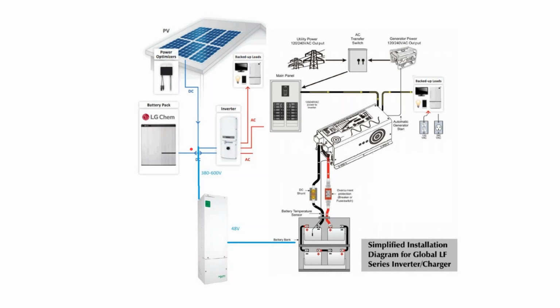So you can program the Solar Edge inverter not to charge and discharge its battery for daily consumption, but instead to only turn on if your load goes above 40 amps. That way you could have a lithium-ion battery providing spiky loads and a lead-acid battery bank providing base load.